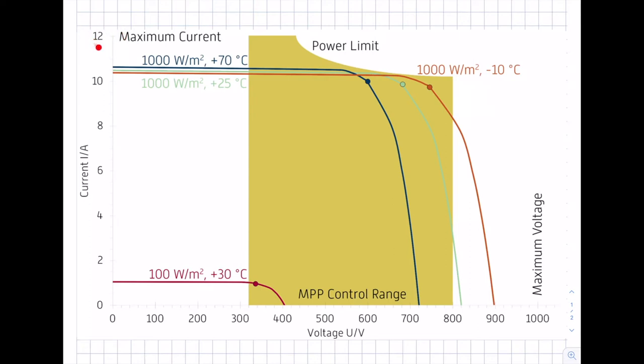This value depends on the type of inverter, while the maximum voltage is typically independent of the inverter type. There is also a third limit: a power limit. The inverter cannot handle unlimited power. The number of modules determines the power of your PV generator, and you have to select the correct power rating for your inverter.